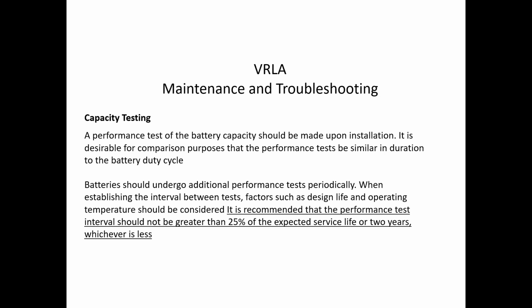The batteries that are being deployed, this last generation of batteries, and I'm talking batteries manufactured within the past 5 years, are far, far more reliable and more predictable than what was originally deployed. But because of those initial batteries and all the issues surrounding them, and it was a nightmare when they were first released, the valve-regulated batteries back in the 80s, IEEE said you really got to test these things every 2 years. That's the recommendation.